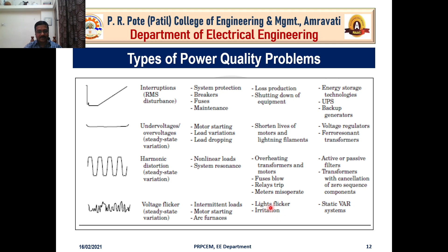These are the voltage flickers, due to intermittent loads, or motor starting, or furnaces where you are melting aluminum. The major effect is that your lights flicker, which creates irritation to the human eyes. You can use static VAR systems here to deal with this power quality issue. So these are the characteristic signatures of several power quality events we have.